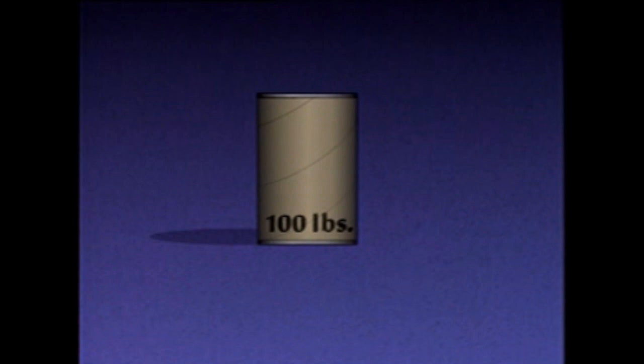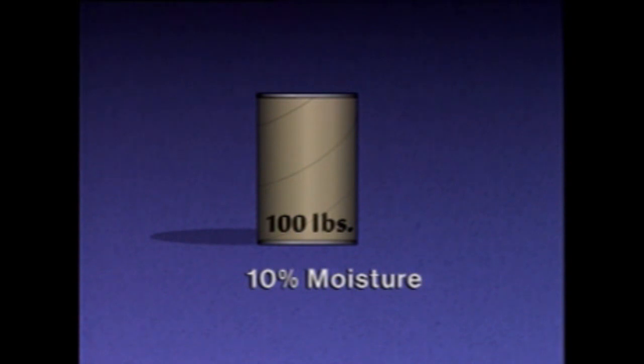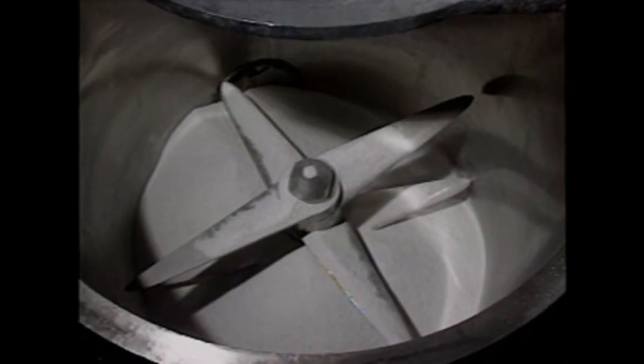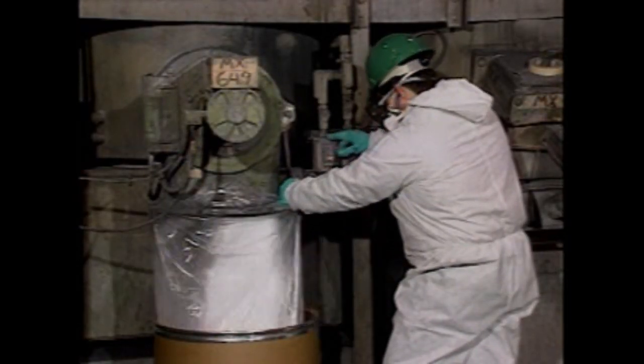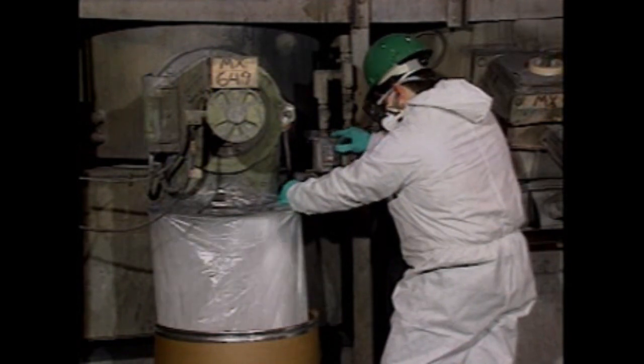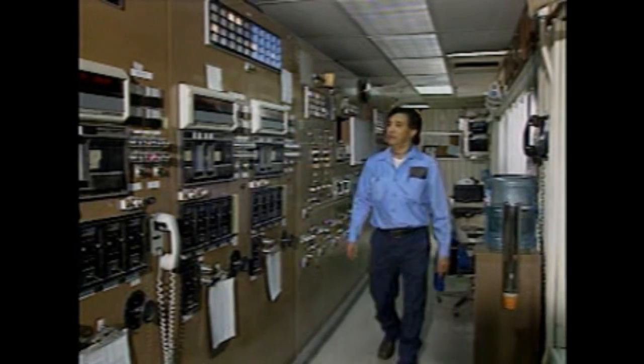An analytical variable similar to humidity is moisture. Moisture is a measure of the amount of water absorbed by a solid material. It can be measured in ounces of water per pound of material, but it's more often measured as a percent of total weight. For example, a moisture measurement of 10% means that 10% of the weight of a material is water, so if there are 100 pounds of material, there are 10 pounds of water. Many process systems are designed to use materials with a specific moisture content — if the moisture content is too high or too low, problems can occur with the process equipment or the product being produced. Accurate moisture measurements can help prevent these problems.